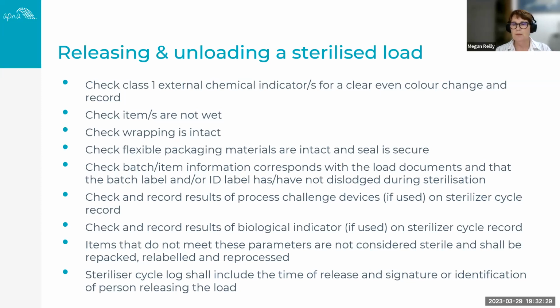Check that the batch item information corresponds with the documentation, so what you've recorded. That's really important. Make sure that if you are using a batch label that you're applying to the package, that it hasn't dislodged during the sterilization process. And any other indicators that you use, record that on the sterilizer cycle record. It's all about, in the event, as I said, if it goes pear-shaped, we can go back and look at every part of the process and be confident that we've met the requirements. If you use biological indicators, then obviously record those on the sterilizer record as well, and record the name of the person who released and unloaded that load.